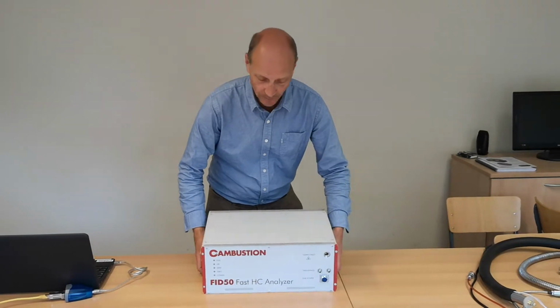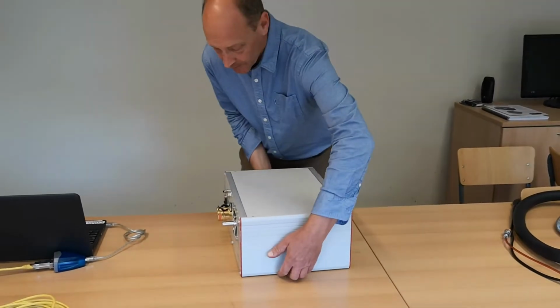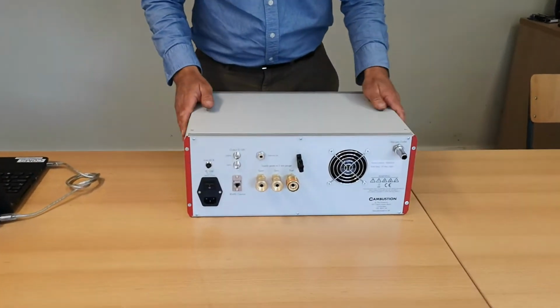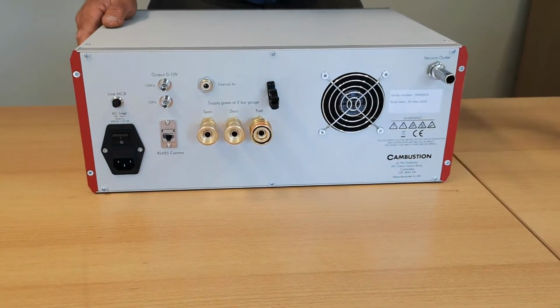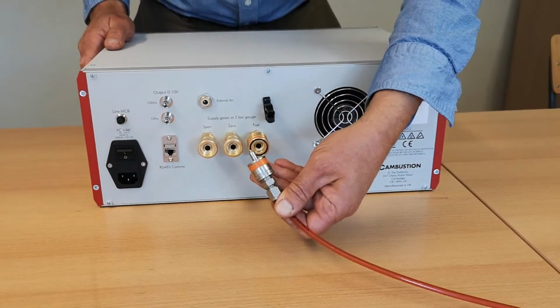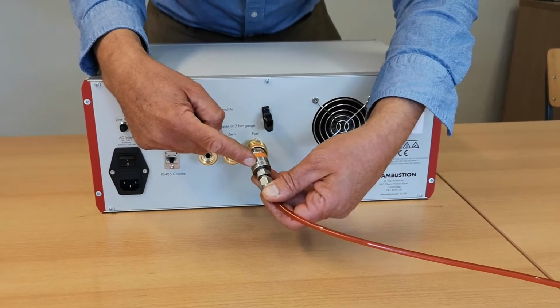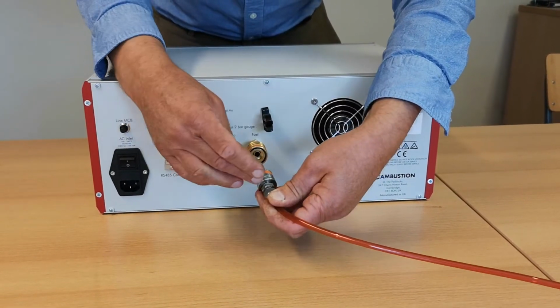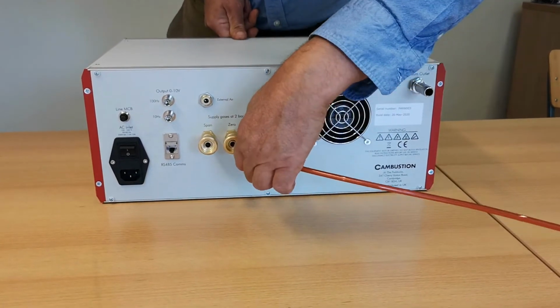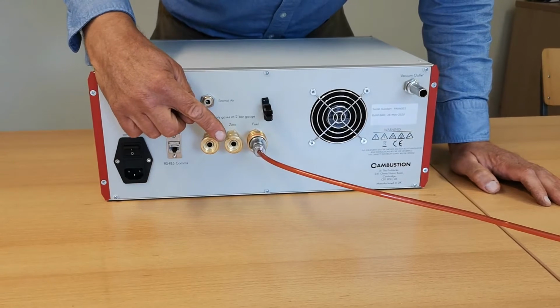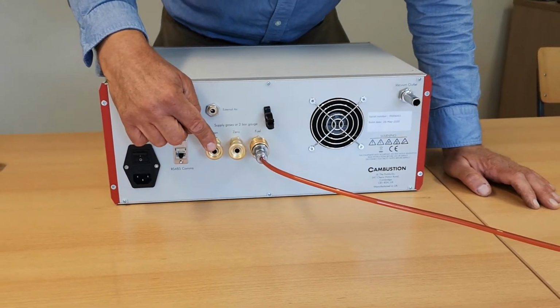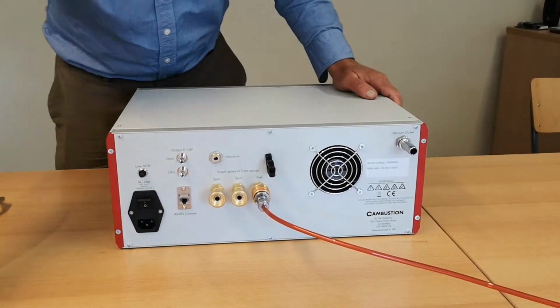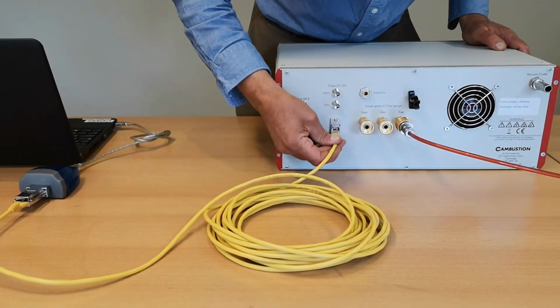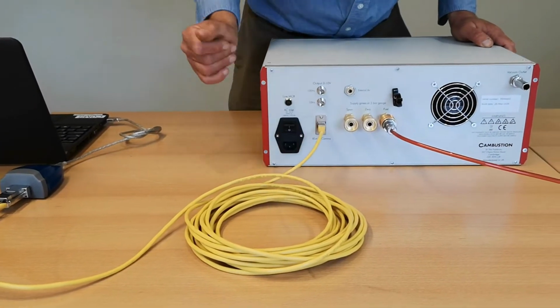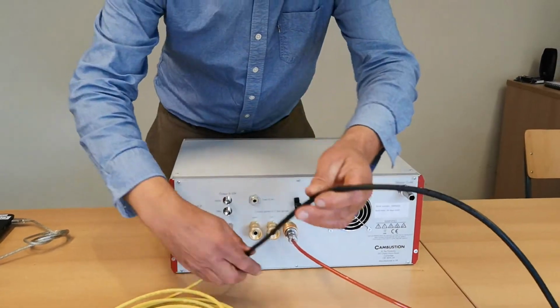So now that the FID50 has been unpacked, I'll show you some of the connections we'll make on the rear panel of the system. There are various things we need to consider. One of the first things we'll connect is our fuel supply. We supplied this orange keyed connector, and we have our flammable gas supply from here. The other two gas fittings are for our zero gas, which is pure nitrogen, and our hydrocarbon calibration gas. We can also attach our communications cable and our main electrical supply.